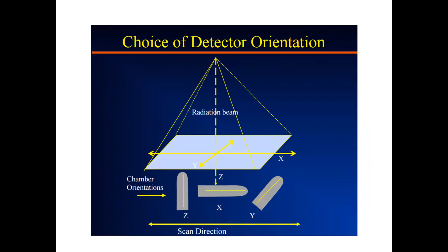We need to keep an eye on all these things during commissioning. Choice of detector orientation is important. We need to establish this while doing the commissioning. Scanning speed, as I already said, affects a lot. And smoothing. So all these things we need to define or make baselines while doing commissioning. All this you learn from experience, and sometimes you need to perform things multiple times to get your desired result, and it requires patience.